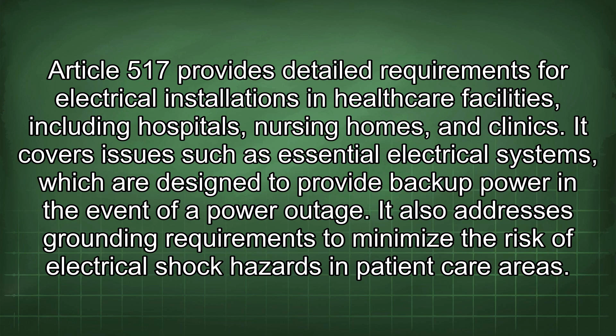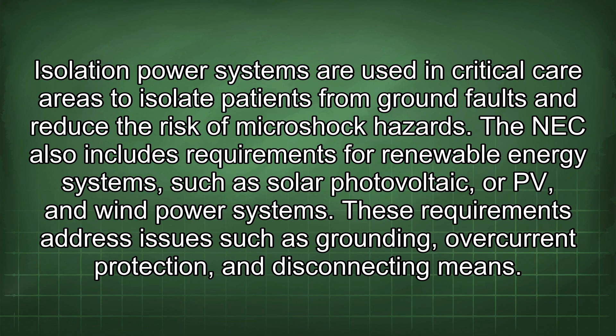Isolated power systems are used in critical care areas to isolate patients from ground faults and reduce the risk of micro-shock hazards. The NEC also includes requirements for renewable energy systems such as solar photovoltaic, or PV, and wind power systems. These requirements address issues such as grounding, overcurrent protection, and disconnecting means. Article 690 provides detailed requirements for solar PV systems, including requirements for inverters, charge controllers, and energy storage systems. Article 694 covers small wind electric systems, addressing issues such as turbine installation, grounding, and overcurrent protection.